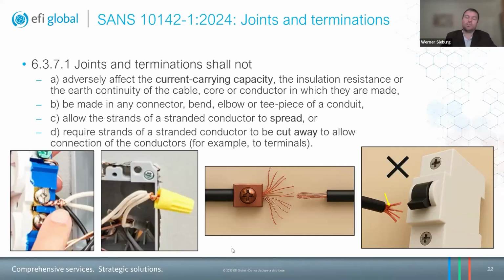So my view is always, if you want to make sure that a joint is made properly, use a crimped ferrule. Use a correctly sized crimper and a correctly sized ferrule, because that piece of metal is going to deform and it will stay in that position, ensuring adequate contact.